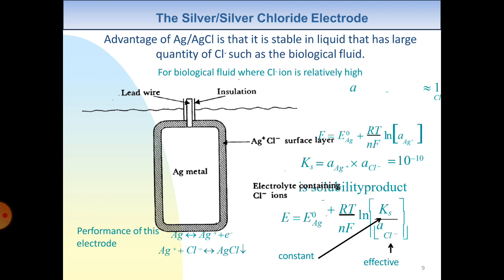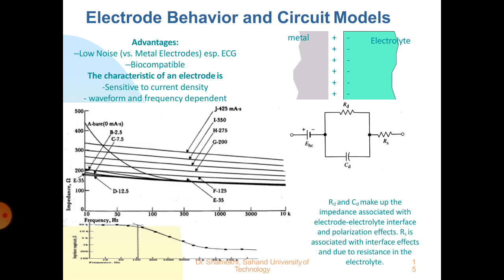This is the surface of the silver-silver chloride electrode. Here the Ag metal has insulation and a lead wire, and the outer side is coated with an Ag⁺ and Cl⁻ surface layer. The electrode contains Cl⁻ (chloride) ions. This shows the electrode behavior and circuit model — the electrical equivalent circuit for the Ag-AgCl electrode. The advantage of the Ag-AgCl electrode is low noise, and its characteristics include sensitivity to current density, waveform, and frequency dependence.